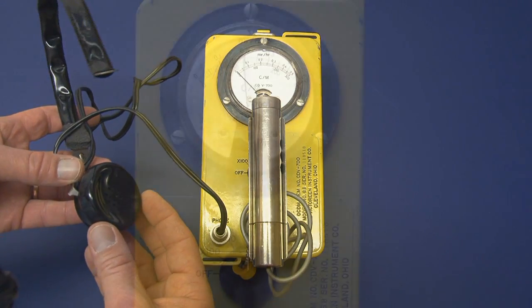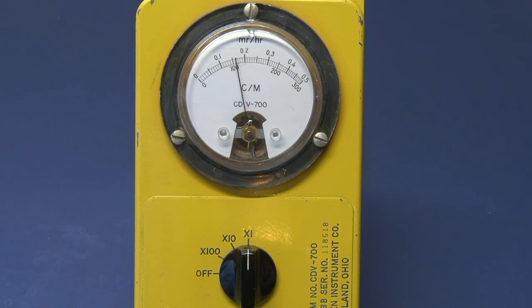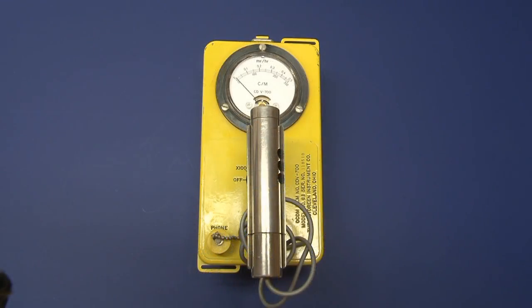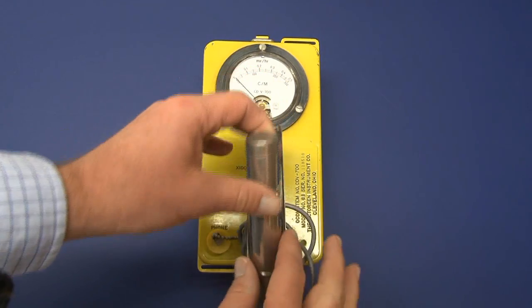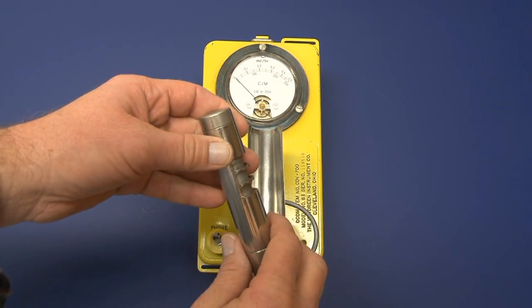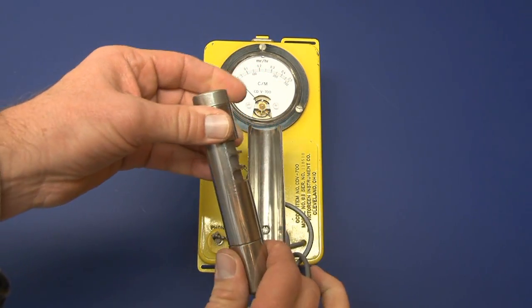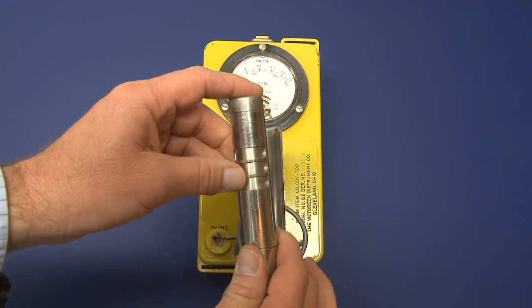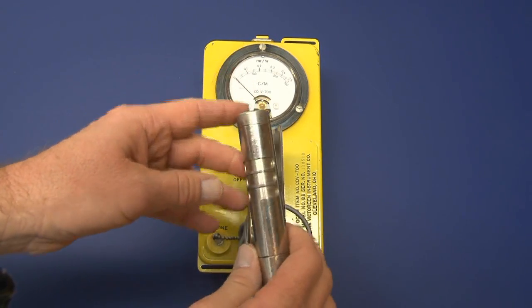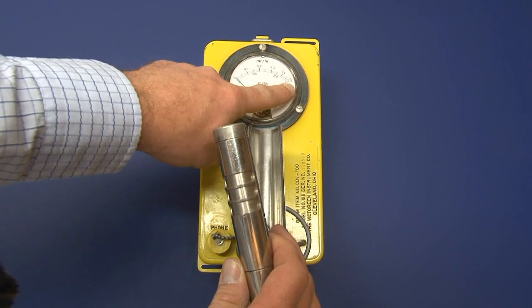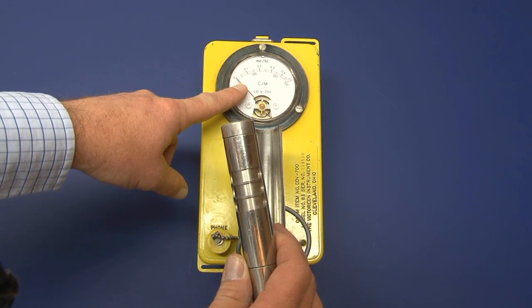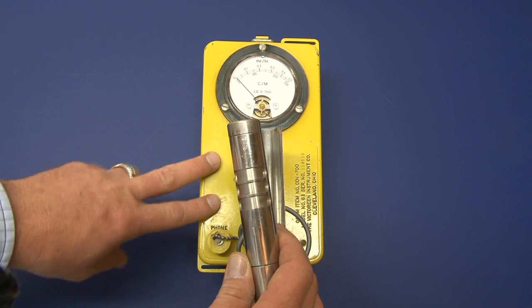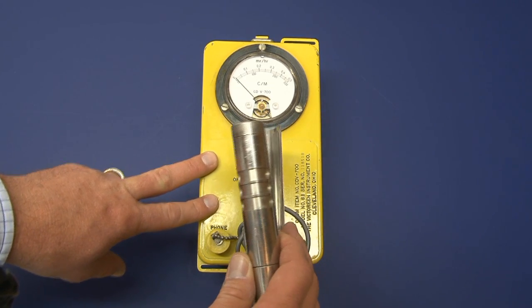I do want to point out one limitation on this instrument. It can happen in radiation levels above one R per hour, that would be a thousand MR per hour. What can happen is the instrument's GM tube can saturate or jam, and then the needle would peg out and then fall back down to zero or near zero, leading the user of the instrument to believe that they're in a safe area when in fact they may not be.